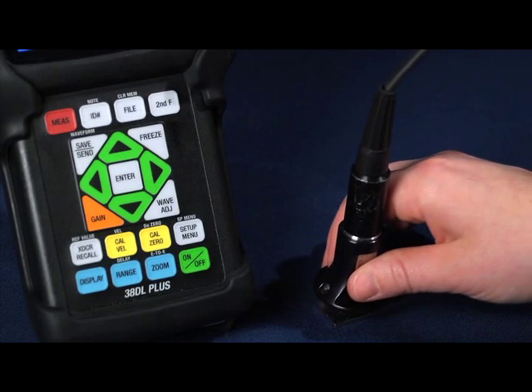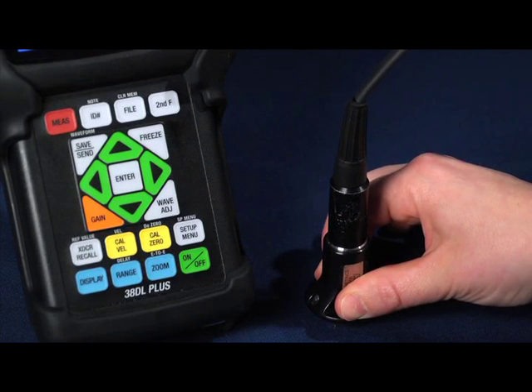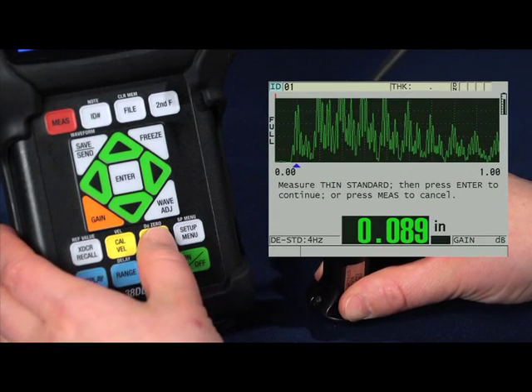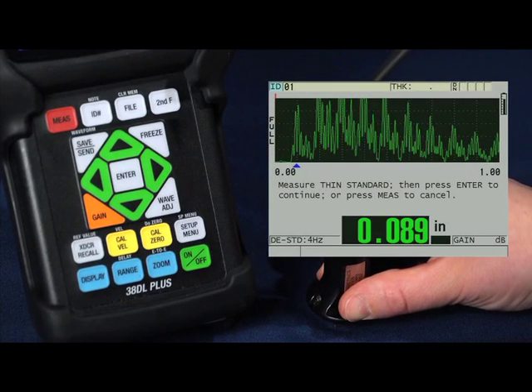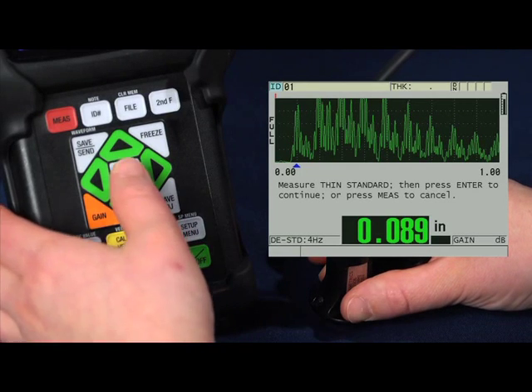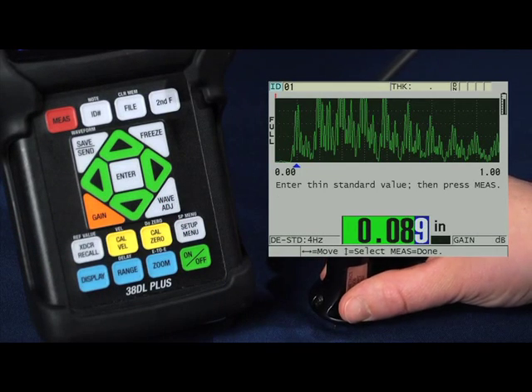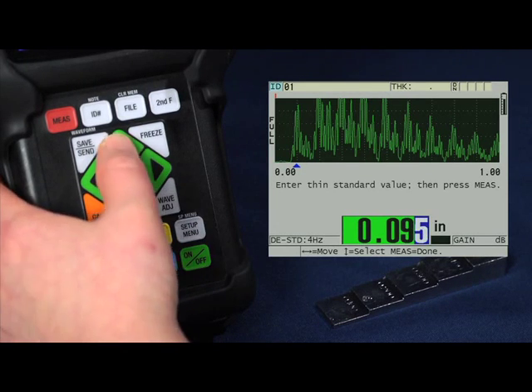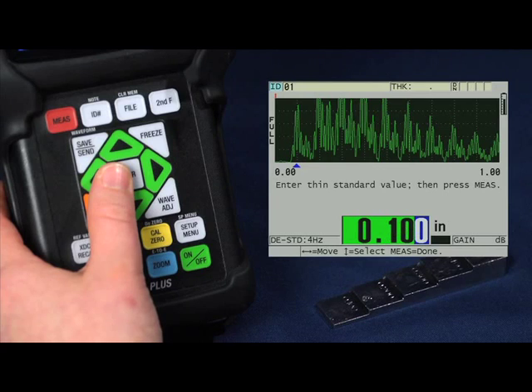Now you can proceed to your thin standard, the hundred thousandths step. Couple onto your thin standard and press the CAL ZERO key. Once you have a steady reading, press the ENTER key. Now again, you can use the up, down, left or right keys to enter in the known value of the thickness standard.